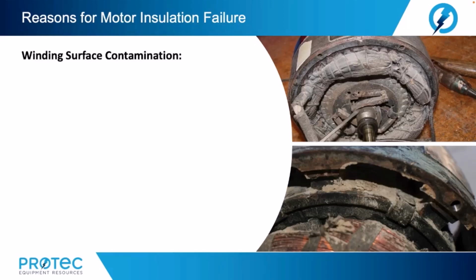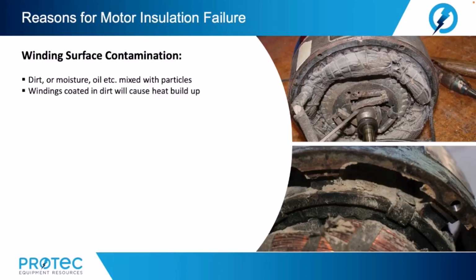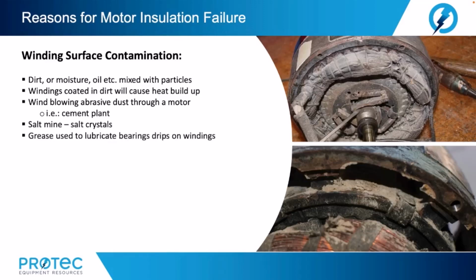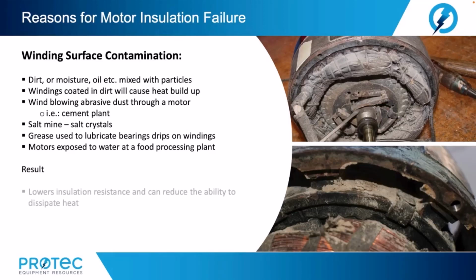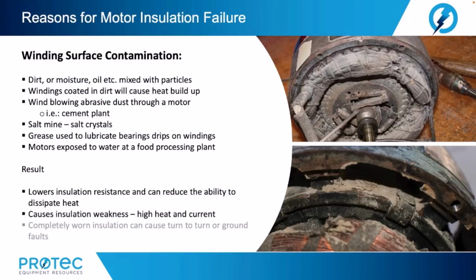All right, let's move on to other insulation failures, such as winding surface contamination, dirt or moisture, oil, etc., mixed with particles. Windings coated in dirt will cause heat buildup. Wind blowing abrasive dust through a motor, for example at a cement plant, can lead to surface contamination. In salt mines, we might have salt crystals. Grease used to lubricate bearings can drip on the windings. Motors exposed to water at a food processing plant can lead to surface contamination. Well, the results: lower insulation resistance and can reduce the ability to dissipate heat. Causes insulation to weaken, high heat and current. Completely worn insulation can cause turn-to-turn or ground faults.